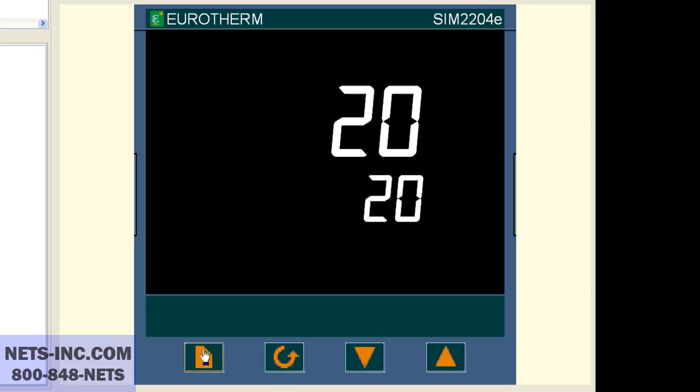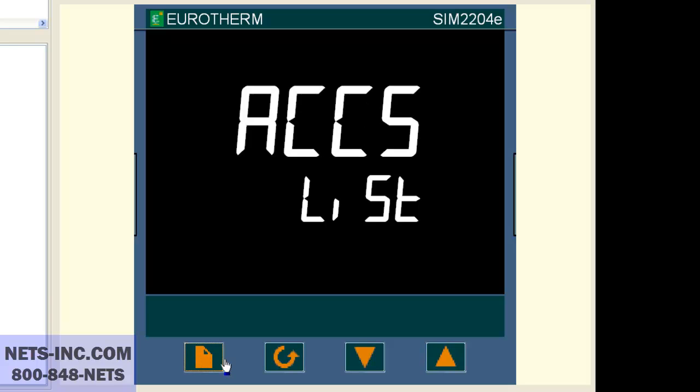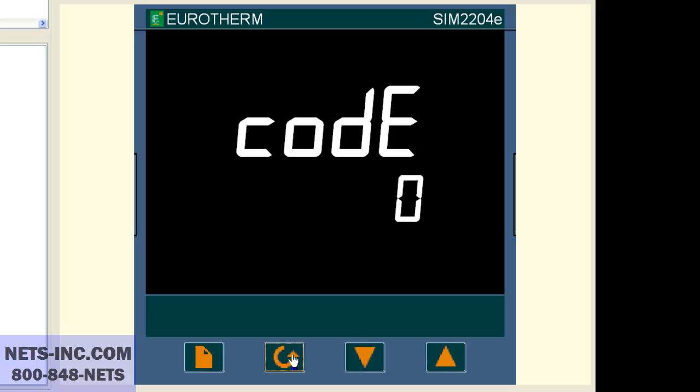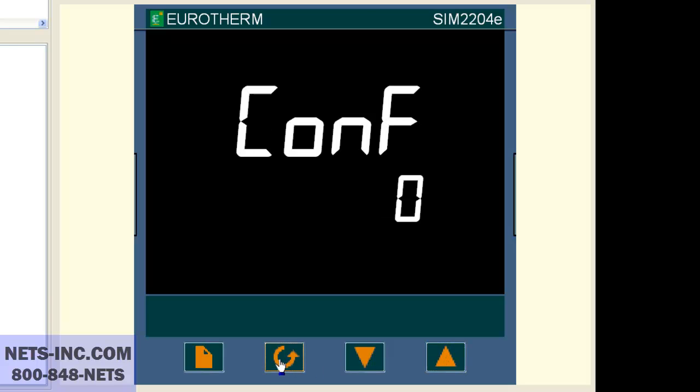Press the page button repeatedly until we see ACCS list. Press the scroll key once and you will see code zero or code pass. With the up button, change the value to one. Now press the page button and the display will change to ConF. Press the scroll key once and you will see code zero. With the up button, change the value to two.